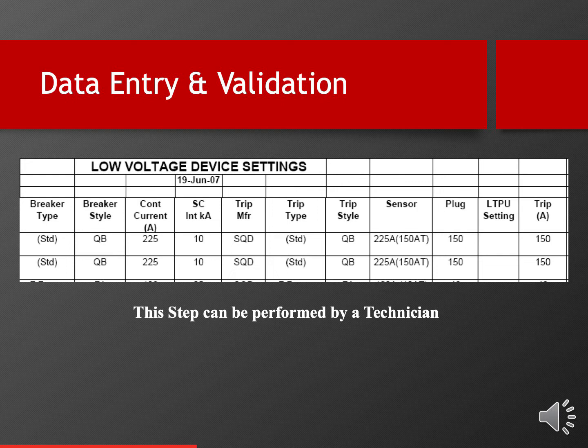So from an engineering standpoint, it's useful from that perspective. From a troubleshooting standpoint, for the workers, we can also tell if somebody has changed the settings in the field. And you can simply compare what you see on this spreadsheet to what you actually see out in the field. And if there's any changes, that means those have been changed since the study was done. And I'll talk about the significance of that from an incident energy standpoint later in the presentation. And this step also can be performed by a technician. Gathering the data and inputting the data can easily be done by an electrician.